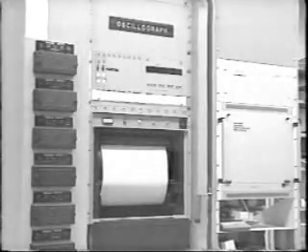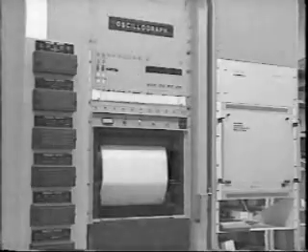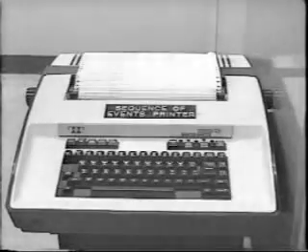Fault data is recorded automatically on oscillograph machines and sequence of events recorders. An oscillograph machine starts automatically when a fault occurs. It records waveforms of selected voltages, currents, and communication signals.